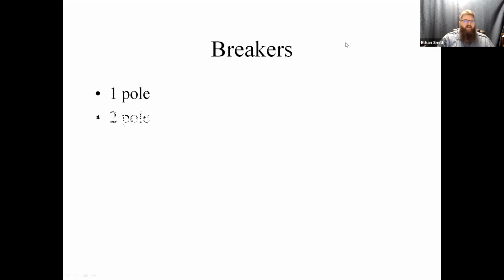Breakers, guys, we already kind of talked about. They come in lots of flavors. 1, 2, or 3 pole breakers typically is what we're going to see. HVACR rated breakers. There is a big trend in our industry and local municipalities to require GFI breakers on condensing furnaces, which I suppose makes sense to somebody because we have a water generating appliance. They want to have a GFI on it. The only place that falls down is when we have a variable speed motor in it of any variety, whether that's an inducer motor or a blower motor, or the new constant torque motors as well. They do not get along with GFI breakers because they are frequency driven motors. They reference the ground for their operations and they will trip GFIs. So when we talk about HVACR breaker, it's rated for HVAC equipment.